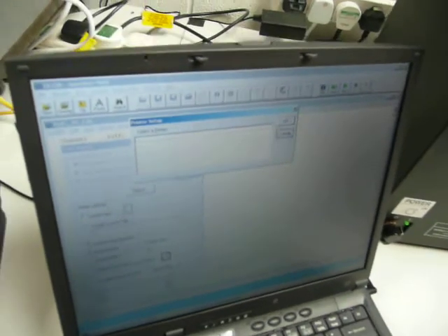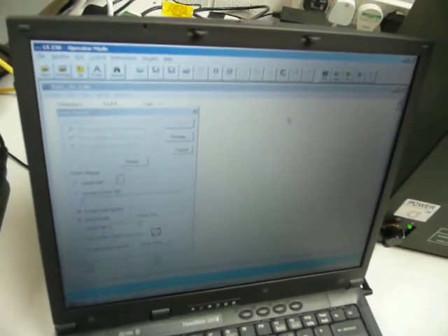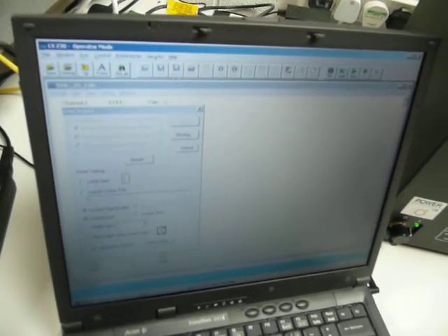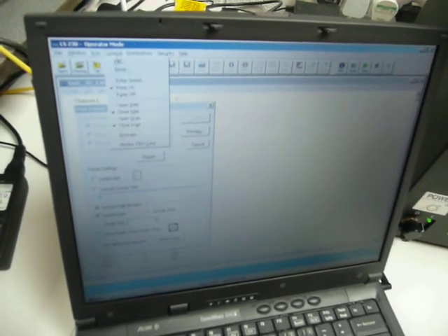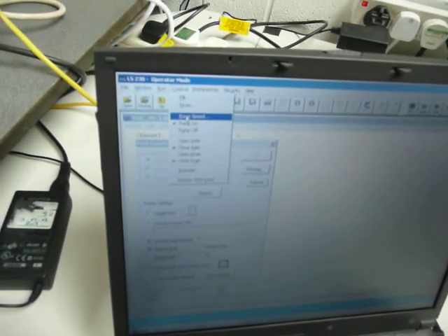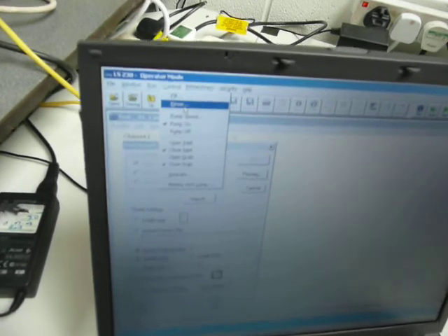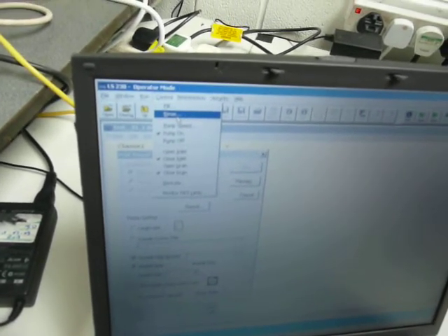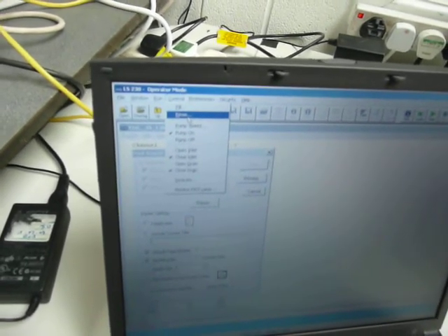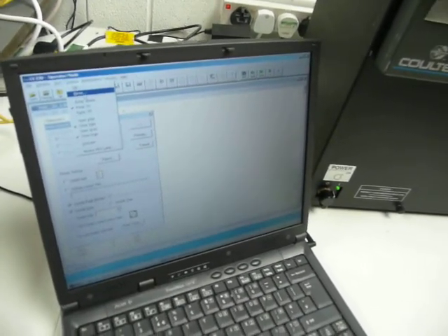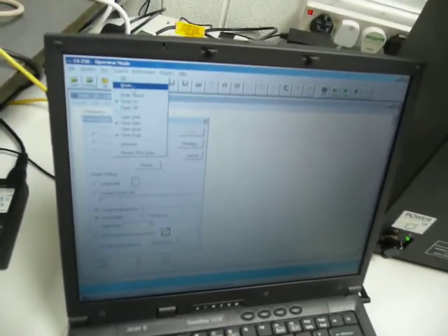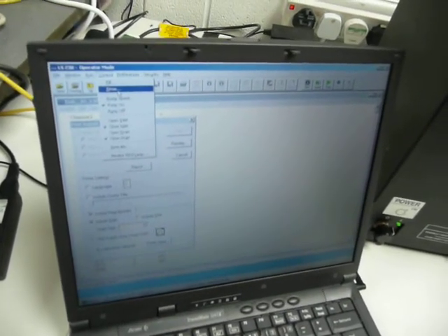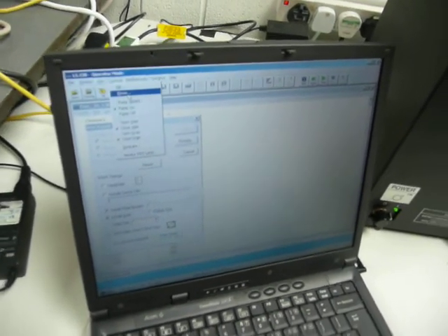Okay. And that's pretty much it, is it, on that one? Yeah. Once you finish the sample, you can go up to control and then press the rinse. Okay. And it will automatically, if it's plumbed into the water, rinse itself until you tell it to stop. And if we press that now without a tube on, presumably it would go all over the bench. Yes. Okay. So we'll do that now. And that's pretty much the end of the video, I guess.